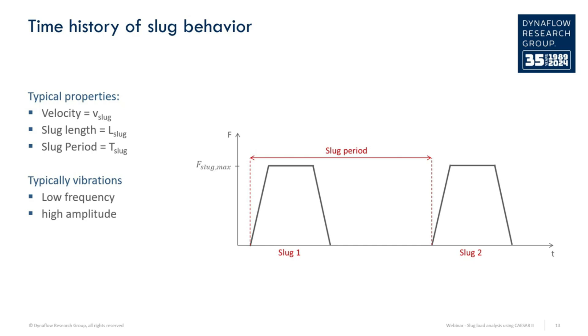Vibrations from slugs often are related to low frequencies and high amplitudes. These frequencies can sometimes be related back to the slug period, so the time between the two different slugs traveling through the system.